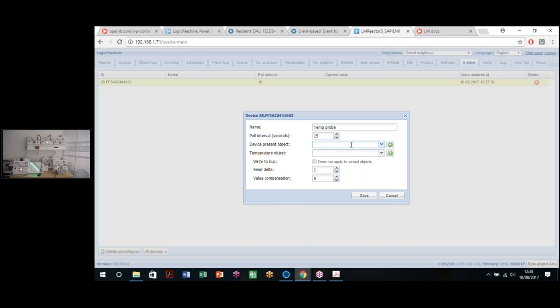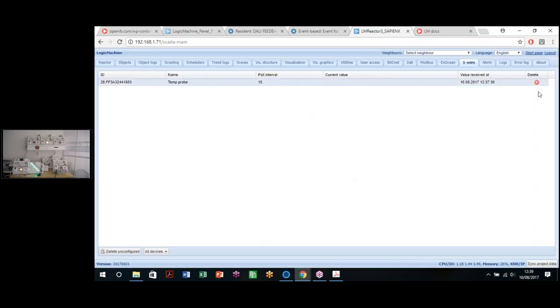Let's create a new object with the address 4211, and a new object 4212. So 4211 will say whether the device is present or not, and 4212 will show the temperature of this object. In this case, we can select if we want to send this information to the bus. And also, we can select which difference of value, in this case 0.2 degrees, will trigger an update of that value. Also, we can set a compensation value for this temperature probe in case we need it. So we save. It will show in white, as we've seen with the other objects.